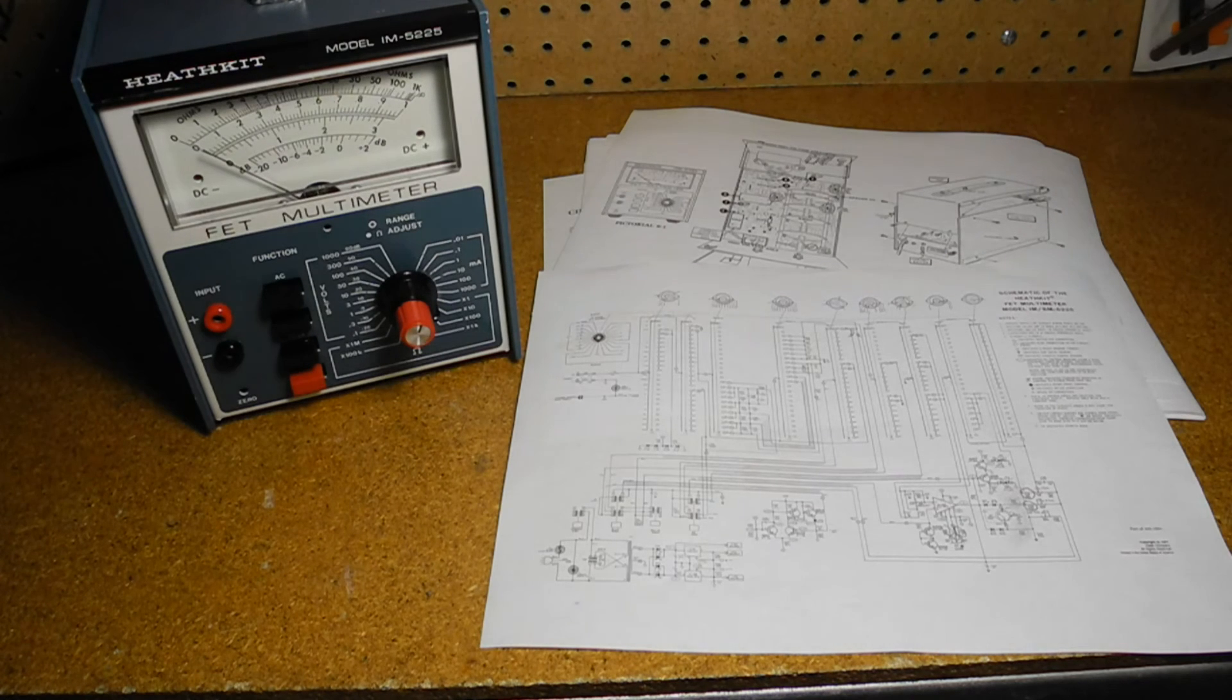R146, a 100 ohm trim pot, measured high at about 168 ohms so I replaced it, but it made no difference. Most voltages appeared to be correct. I swapped the op amp with another one and that did not help. Then I noticed that the resistance of the meter was much higher than normal.